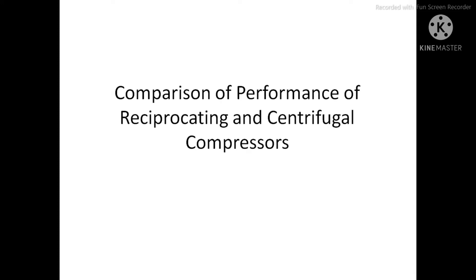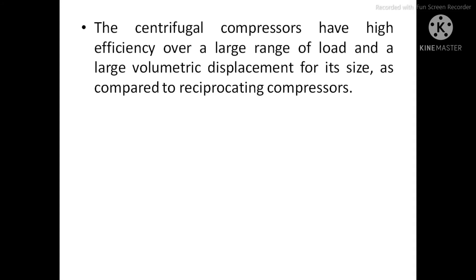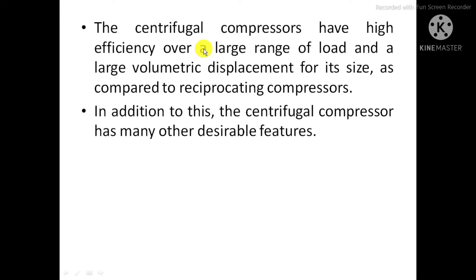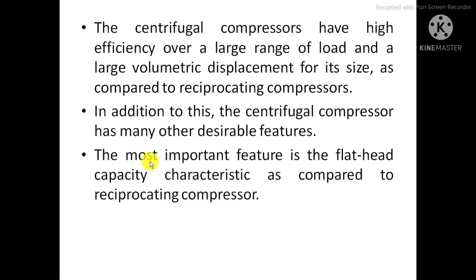Centrifugal compressors have high efficiency over a large range of load and a large volumetric displacement for their size as compared to reciprocating compressors. The efficiency of the centrifugal compressor is greater as compared to reciprocating compressors, and centrifugal compressors also have large volumetric displacement. In addition, the centrifugal compressor has many other desirable features, the most important being the flat head capacity characteristic.